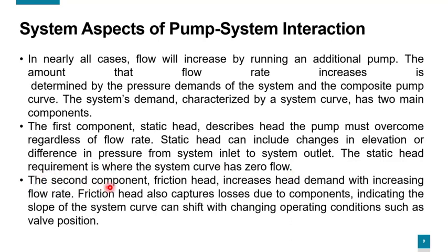The second component, friction head, increases head demand with increasing flow rate. Friction head also captures losses due to components, indicating the slope of the system curve can shift with changing operating conditions such as valve position. So the first component is static head, and the second component is friction head. Static head must be overcome regardless of the flow rate, and friction head increases head demand with increasing flow rate.